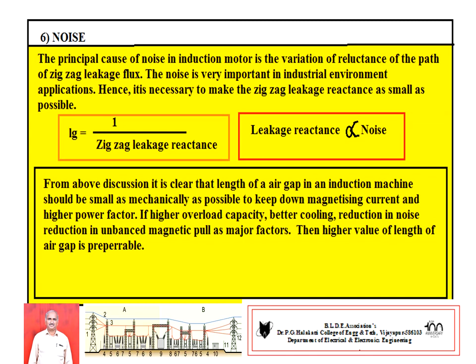On the other side, if we want to design an induction motor with overload capacity or better cooling, or reduction in noise, or reduction in unbalanced magnetic pull, under such conditions a higher value of Lg is preferable.